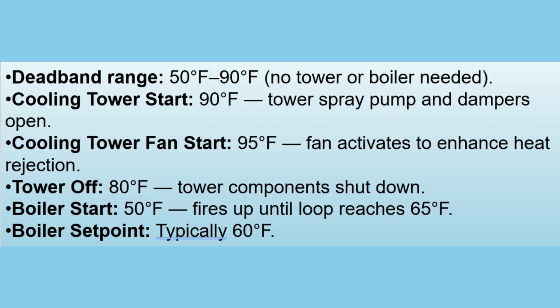Once the temperature drops to around 80 degrees Fahrenheit, the tower pump, fan, and dampers all shut down. On the low side, when the loop temperature falls to 50 degrees Fahrenheit, the boiler starts and runs until the temperature rises to about 65 degrees Fahrenheit. The boiler set point is typically maintained around 60 degrees Fahrenheit. This control sequence keeps the water loop temperature stable year-round, allowing each WSHP unit to operate efficiently while minimizing energy use and unnecessary equipment cycling.